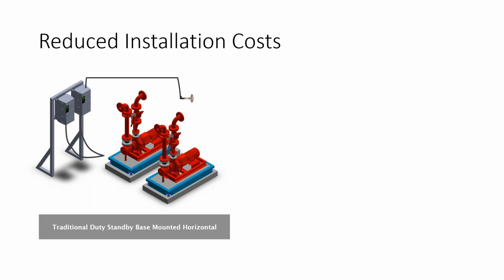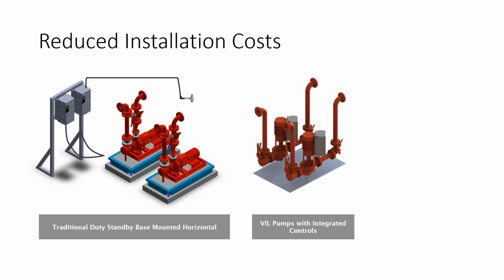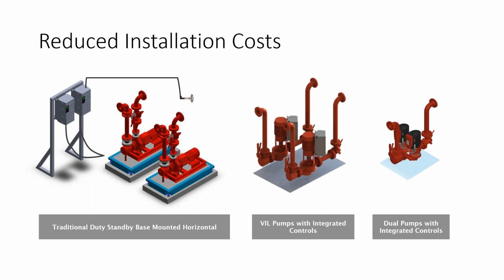Right here, this is your traditional system. You have the VFDs mounted on the wall or a stand. You have the differential pressure sensor, and then the two systems mounted on floor mounts with concrete pads and vibration isolation for each system. Here's your vertical inline pump with integrated controls. You'll see the VFDs have moved onto the side of the motor, which definitely helps save on space, and the layout definitely will give you a lot of savings on the electrician, because he comes and hooks up power to this system and then walks away.